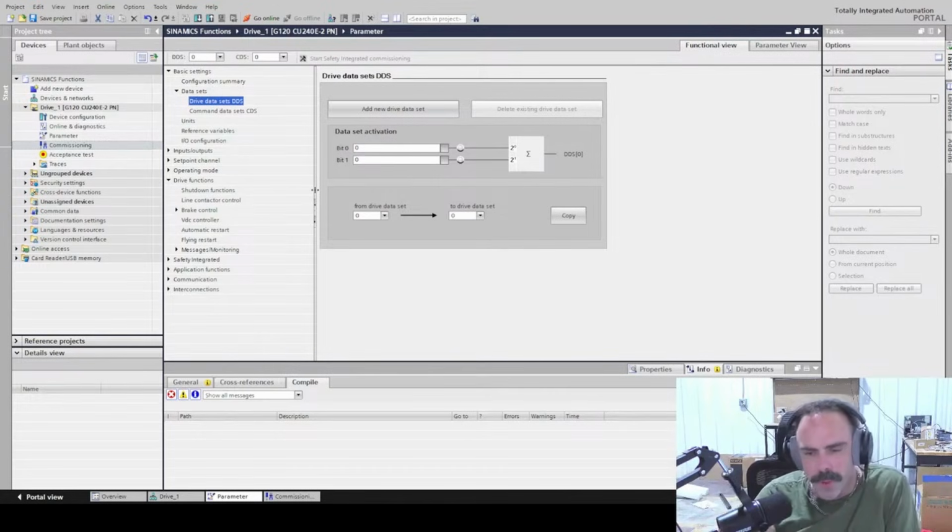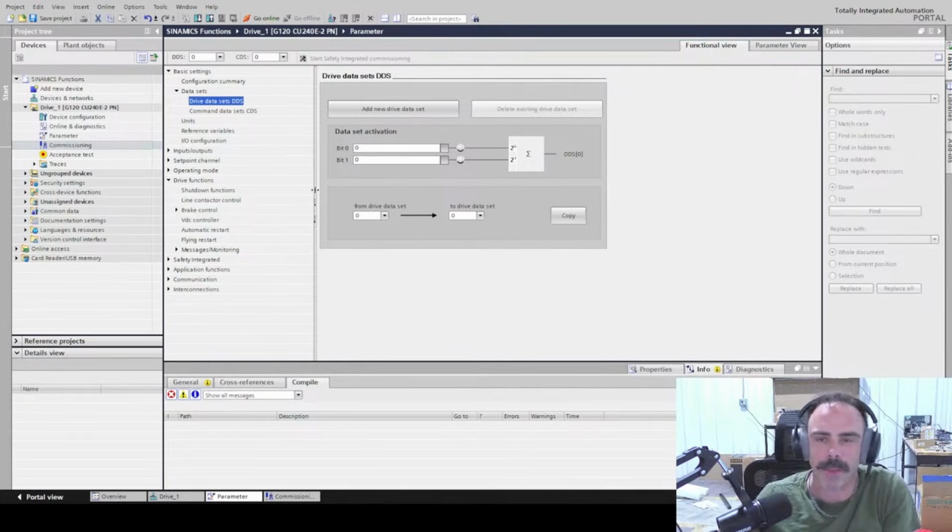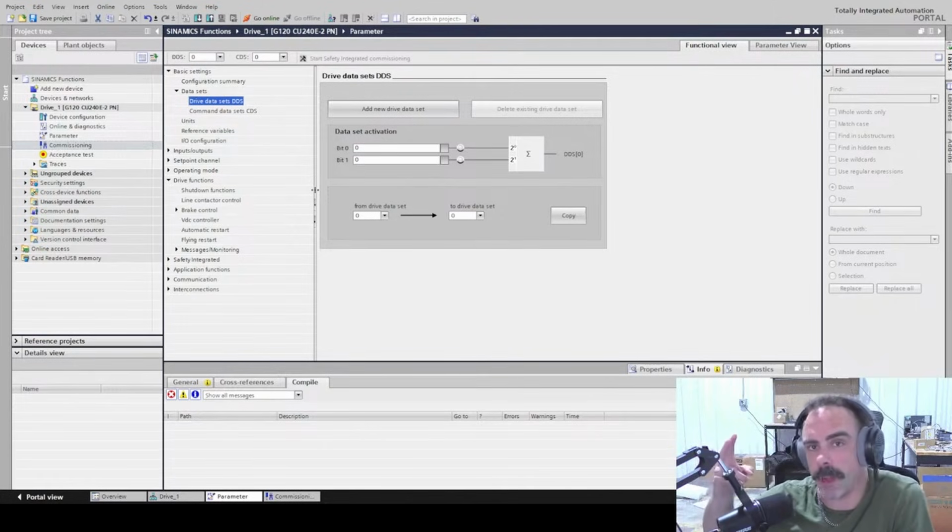So what I did was, all you have to do is have each motor be on a separate contactor. And you say, hey, feeder 1 is contactor 1, right? And then I want to run feeder 1, and it's going to get the drive. So on these 13 motors, 13 feeder screws, there's 2 drives, because you can only ever run 2 of them at the same time.